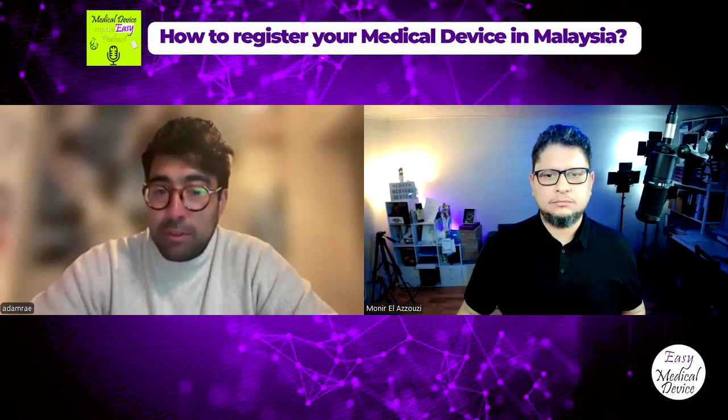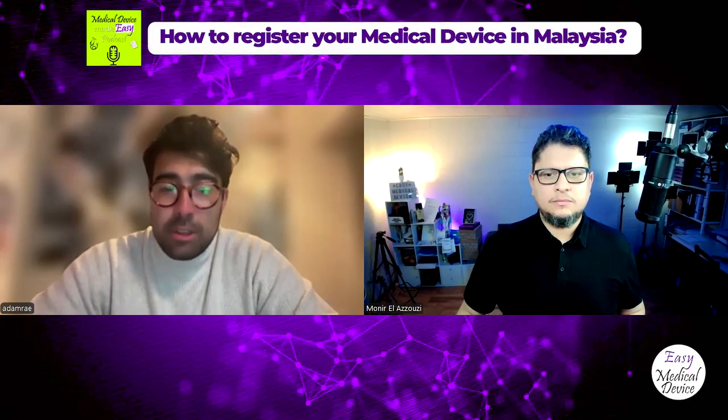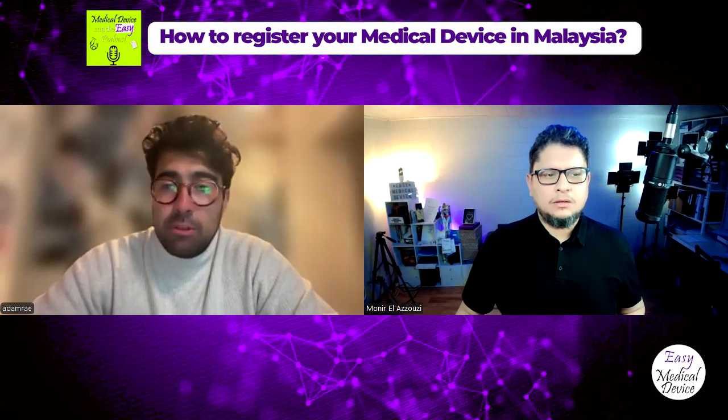You have to have your PMS system specific to Malaysian requirements, which is again not too different, but it's just a bit more. Your technical documentation would need to be in the format of the common CSDT template. So that's the template they refer to. And then they would have to do that full scale verification essentially of that. So there is a massive benefit if you have a device on the market elsewhere, to getting it on the market in Malaysia. You can really benefit from that simplified verification process.